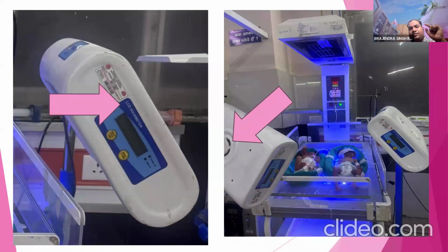Very important, the phototherapy fan should be clean. So this fan, if working, then the phototherapy unit is not going to heat up. If the phototherapy unit does not heat up, then the irradiation part, working part, flux generation part is good. If not working, then flux generation is not so good.